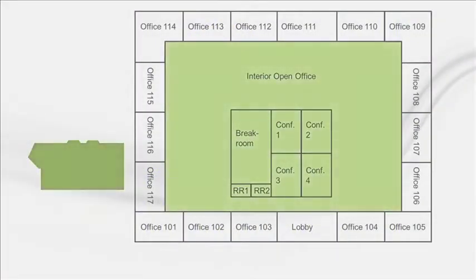Another possibility is to couple the interior zones and the dedicated outdoor air unit on a single VRF heat recovery system. In the summer, they will all require cooling, so the sizing will be dictated by the sum of all the loads. In the winter, the indoor cooling load and the fresh air heating load can be used to offset each other, and energy savings can be realized.